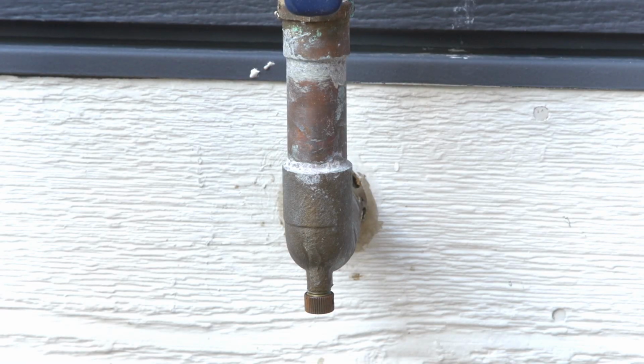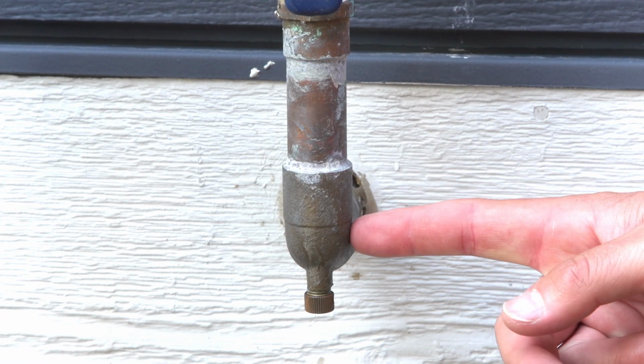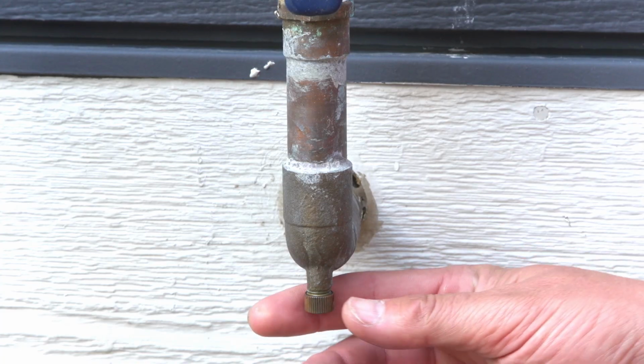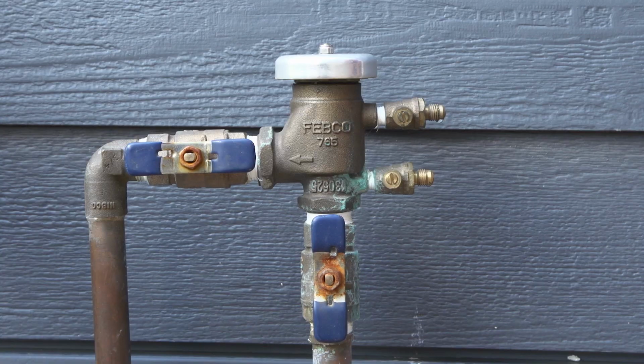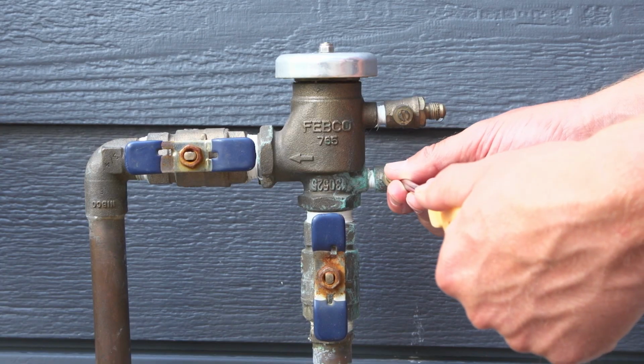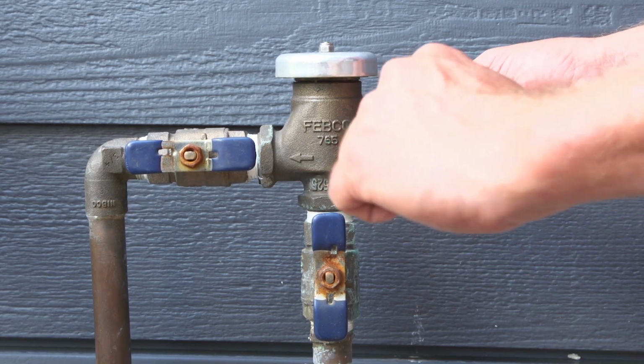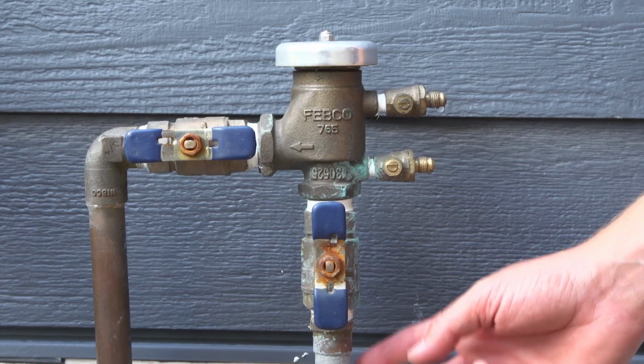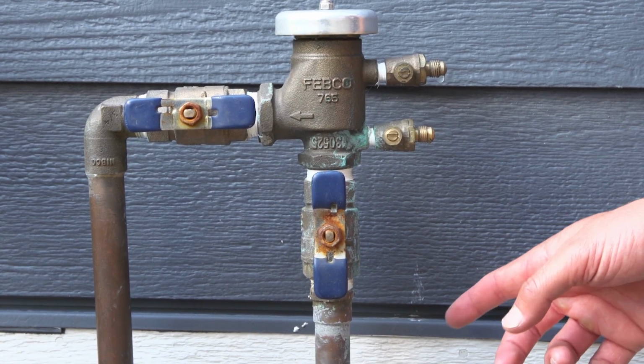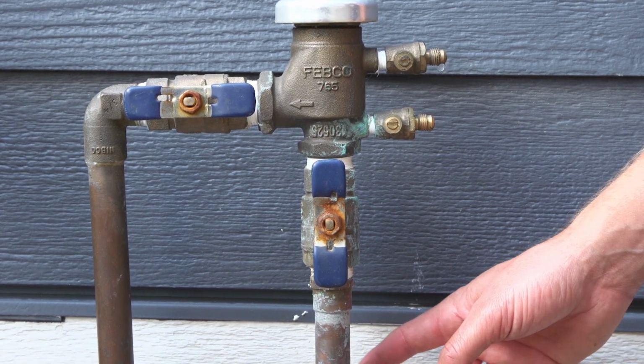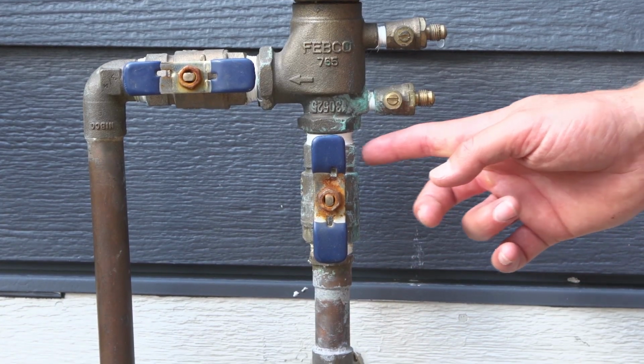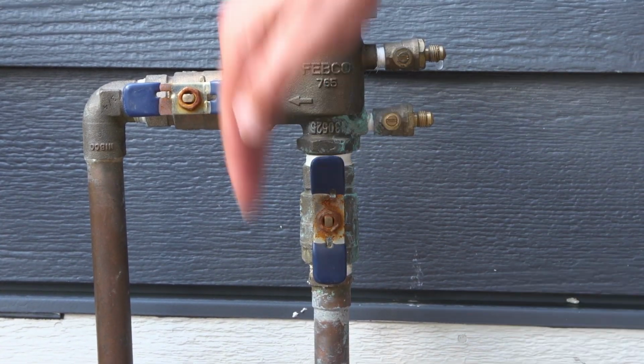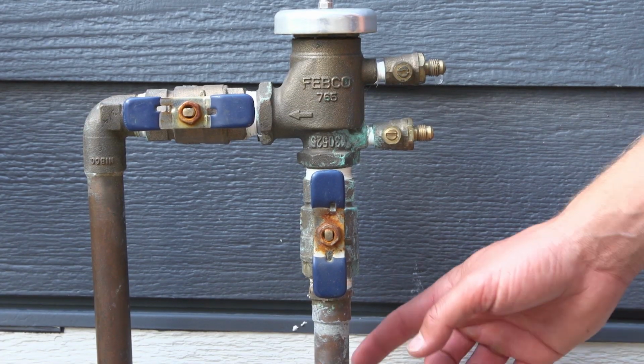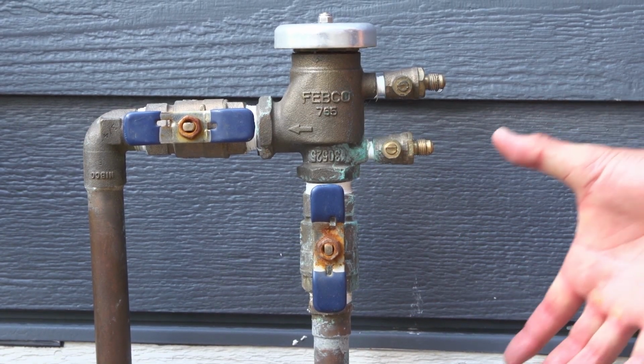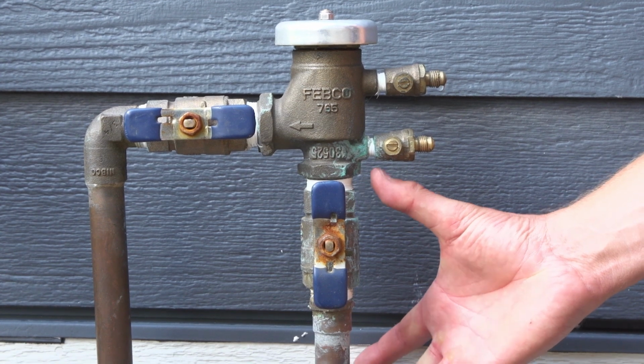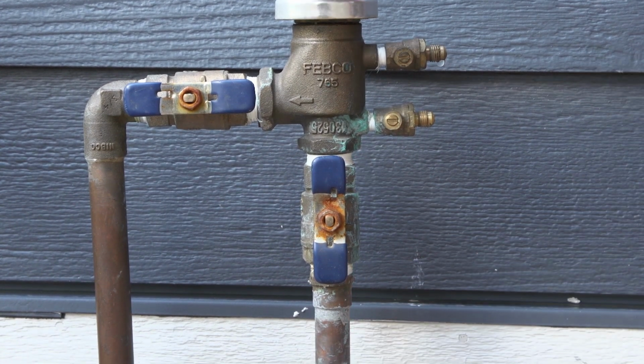Not every system has an external drain, but this one does, and if it does have an external drain, we do recommend leaving this open for the winter. We do recommend leaving the test cocks open for the winter, and the reason is if someone accidentally turns on the water to the sprinkler system, or if the valve doesn't shut properly and a little drip of water goes by every 10 minutes, it will eventually fill this pipe with water, and instead of going into the sprinkler system causing more damage, it will just come out of the test cock, and the only part of the sprinkler system that could have potential breakage would be this portion right here versus the entire system.